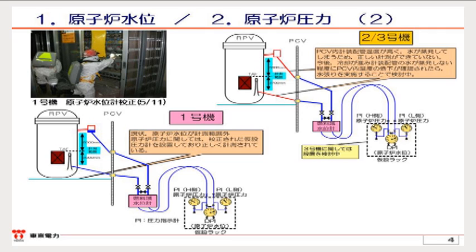The situations of units 2 and 3 are described on the right side. As for Unit 2, we conducted a calibration once, but the water from the L side evaporated and the condensate pot has not been filled with water yet. Therefore, we think that the water level gauge is in imperfect condition. In addition, regarding Unit 3, such calibrations have not been conducted. We will develop an appropriate work plan to continuously conduct water filling in the condensate pot. Also, branching at the L side enables us to measure the pressure in the reactor. Please proceed to the following page.